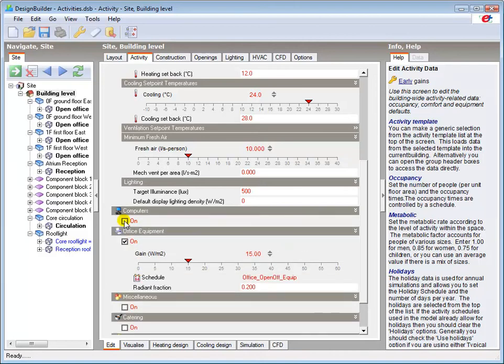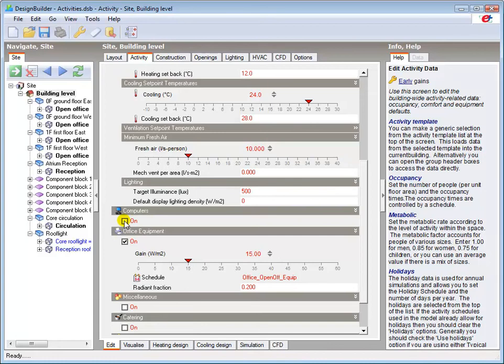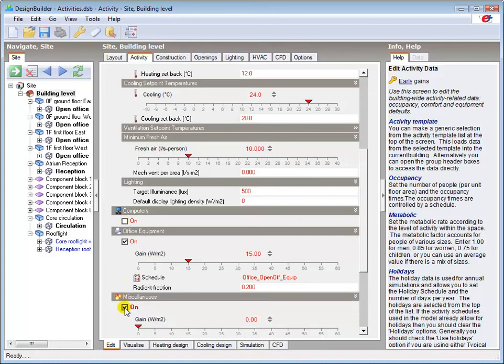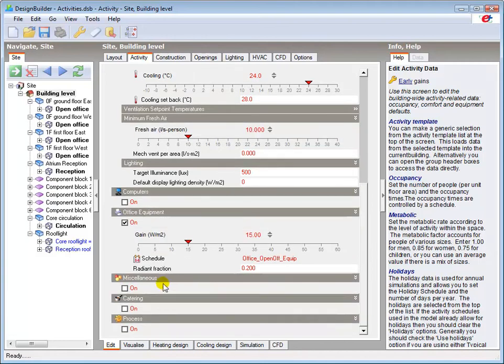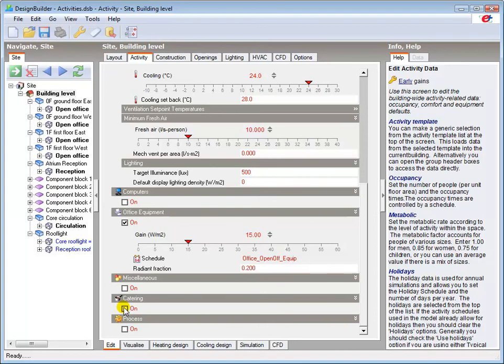Additional significant gains not related to typical small-scale office or IT equipment, e.g. large multifunctional copiers or vending machines, may be input under the miscellaneous header. Any catering or process loads can be input under the respective headers, although these would normally be separately zoned with the appropriate activity template assigned.